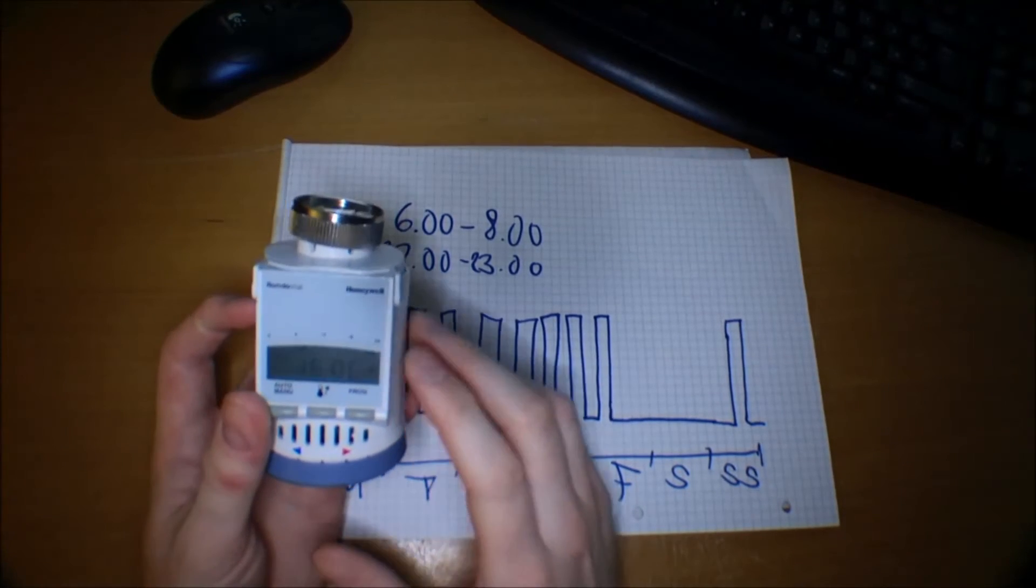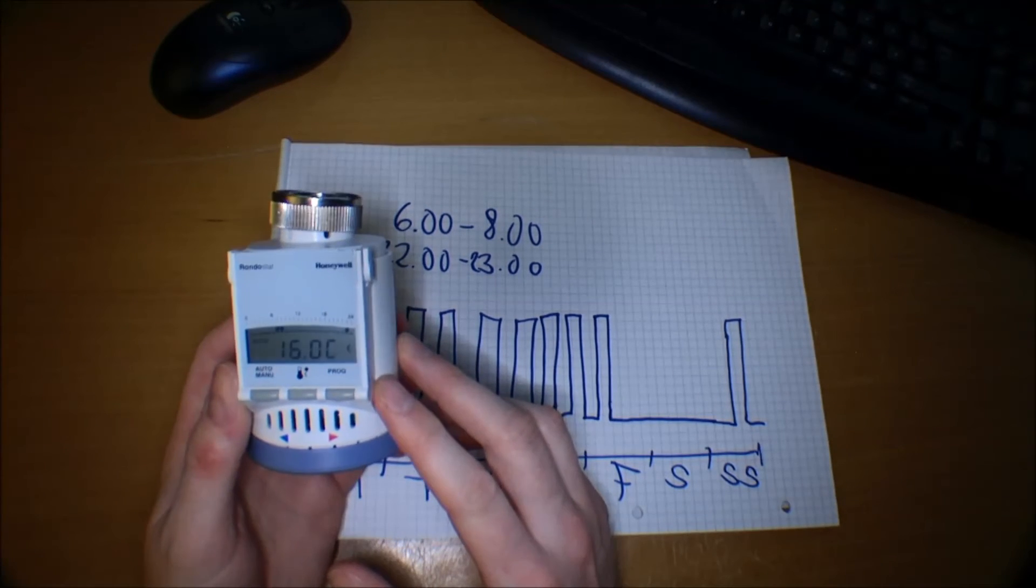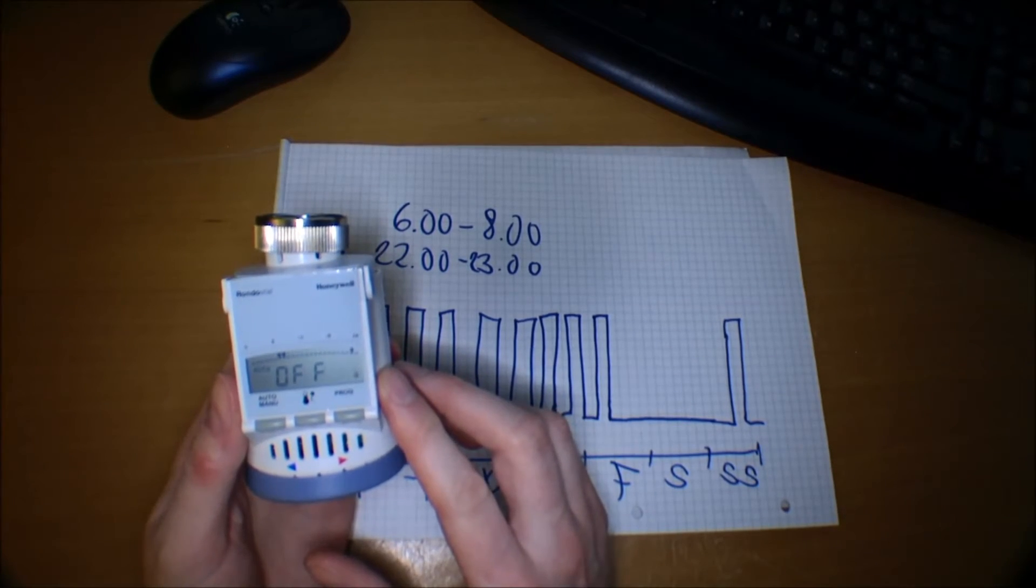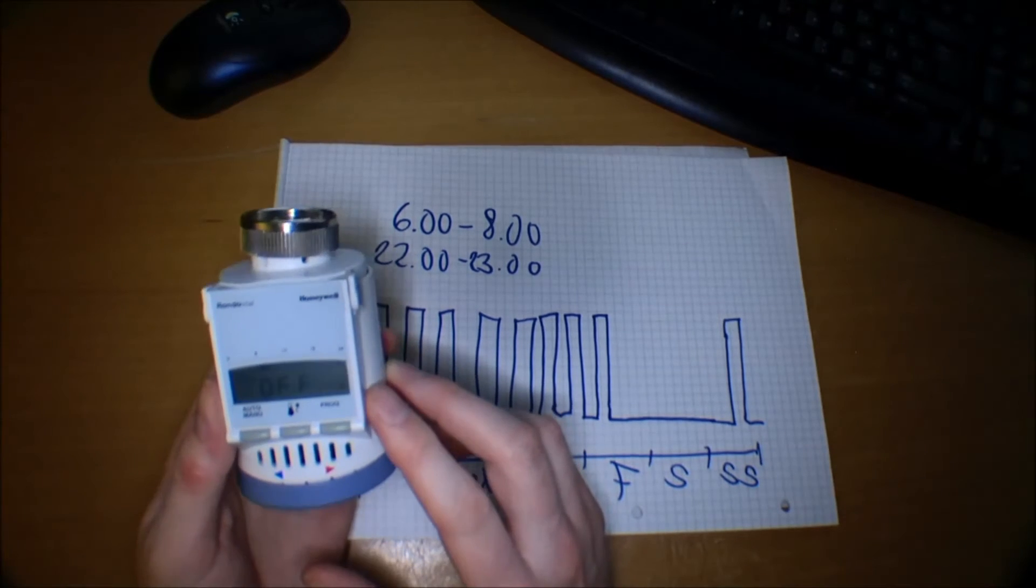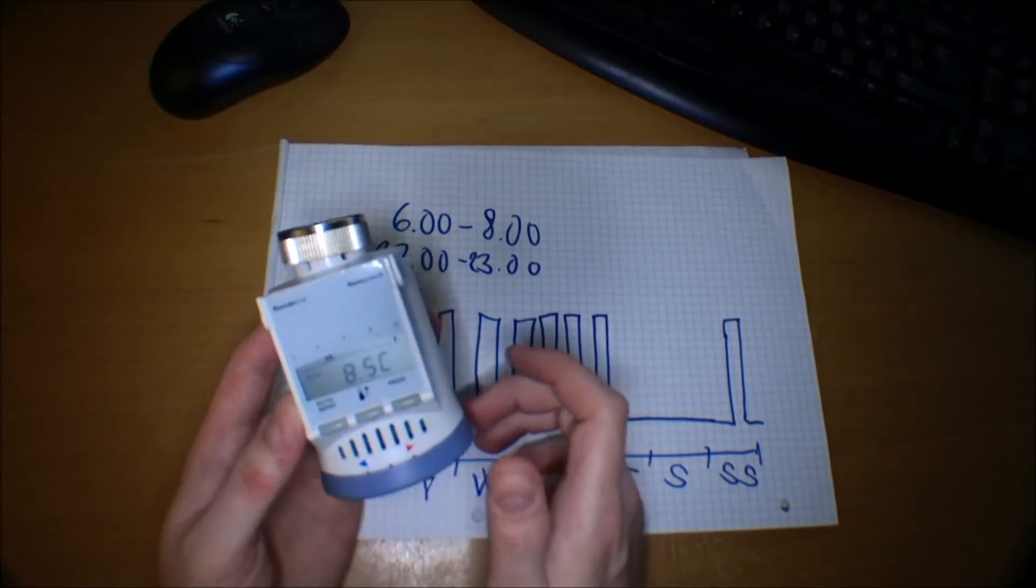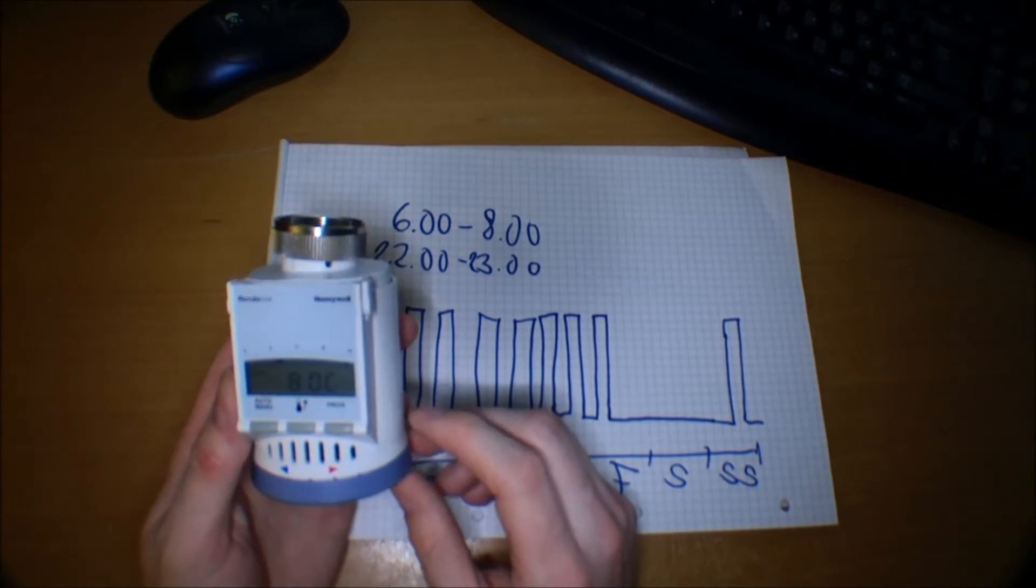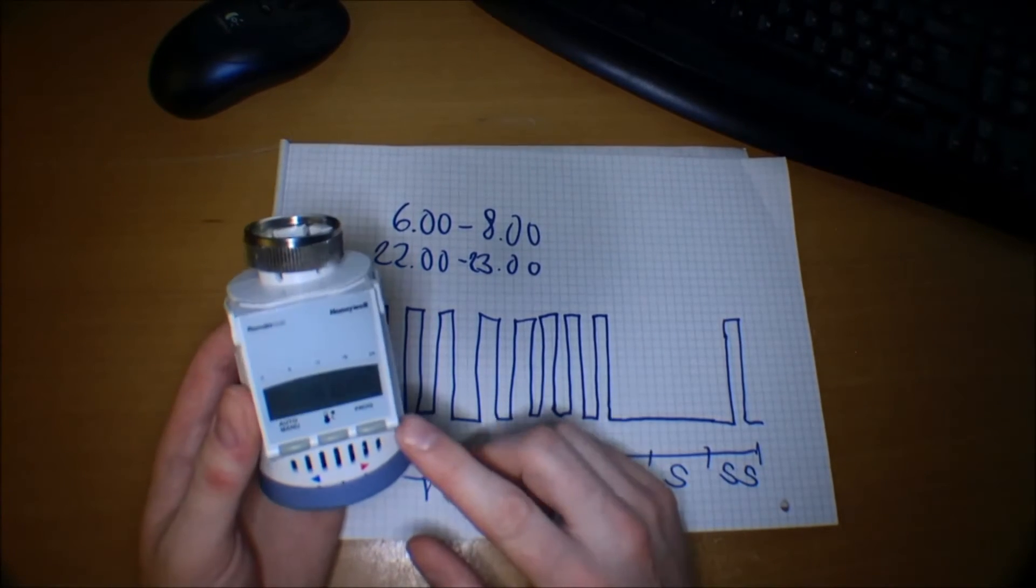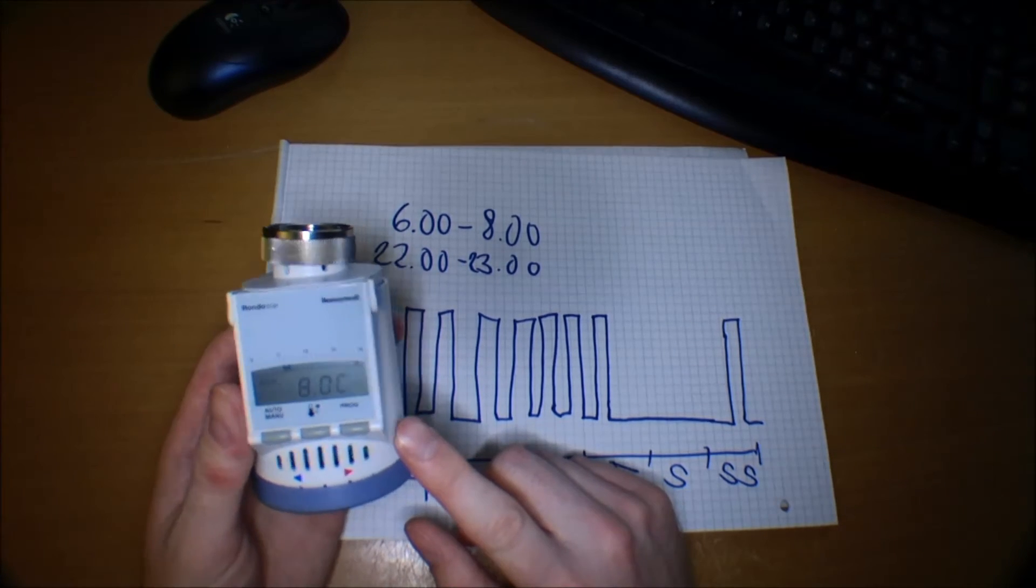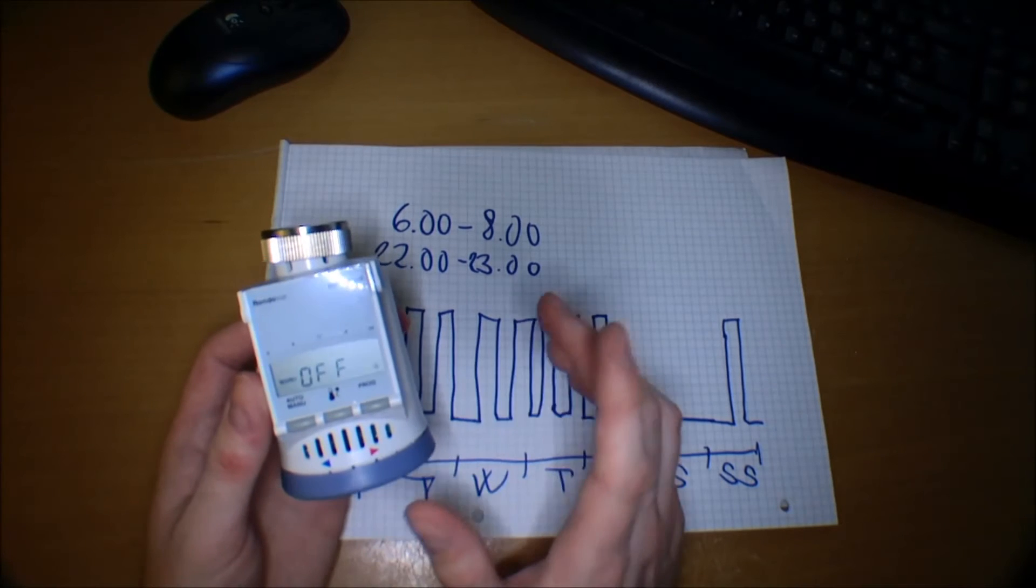The Honeywell Rondostat thermostat has a frost protection as well. Even though the thermostat might be off, if the temperature gets below 4 degrees it will turn on until the temperature is back over 6 degrees again. So it will keep the system free of frost and it will do this even if it's set to off. It doesn't matter what mode it's in, it will keep the house free of frost.